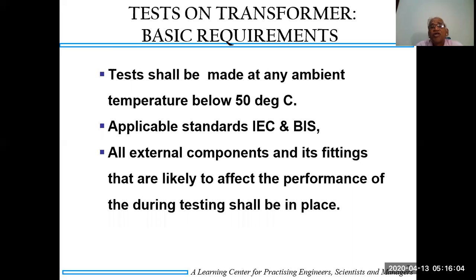Now, tests on the transformer, basic requirements. A test shall be made at any ambient temperature below 50 degrees centigrade. Application standards will be either IEC for international or Bureau of Indian Standards, and all external components and fittings that are likely to affect the performance during the testing shall be in place.